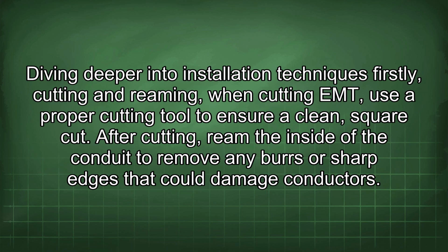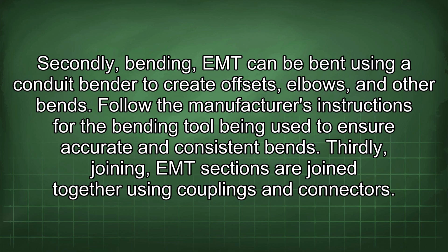Firstly, cutting and reaming. When cutting EMT, use a proper cutting tool to ensure a clean, square cut. After cutting, ream the inside of the conduit to remove any burrs or sharp edges that could damage conductors. Secondly, bending. EMT can be bent using a conduit bender to create offsets, elbows, and other bends. Follow the manufacturer's instructions for the bending tool being used to ensure accurate and consistent bends.